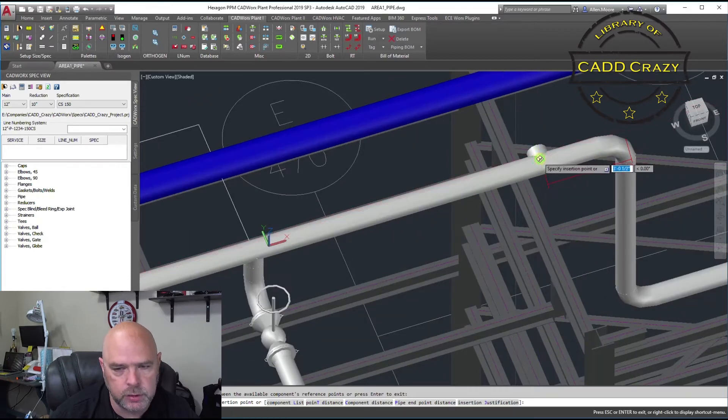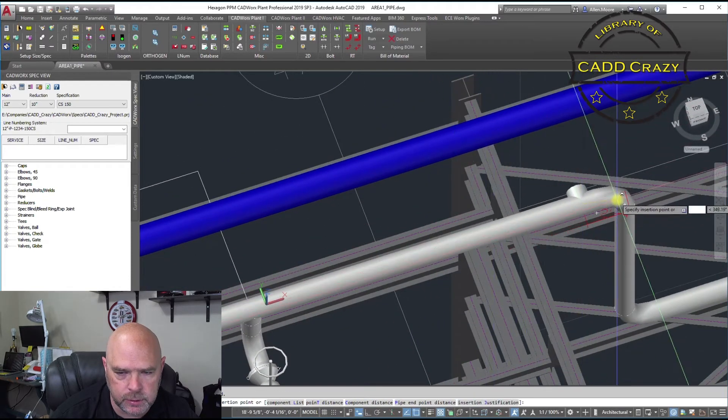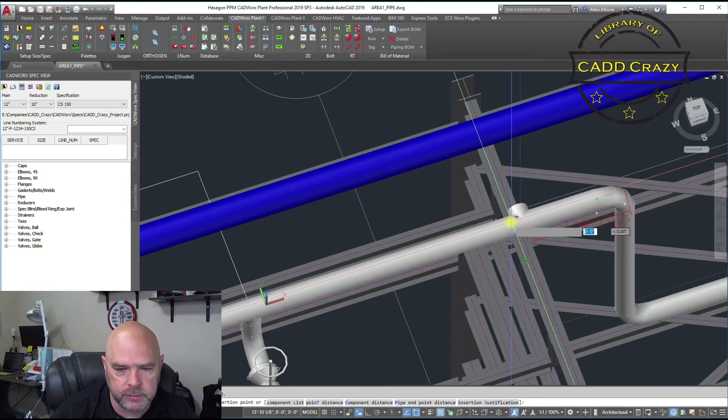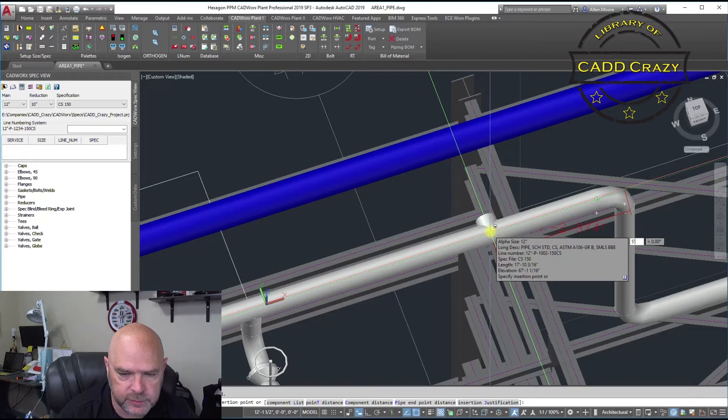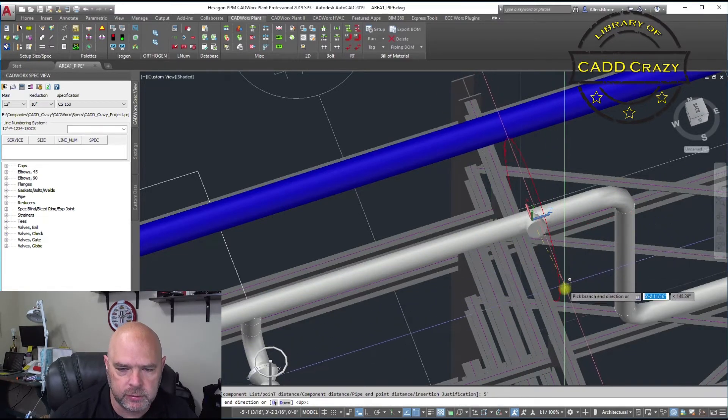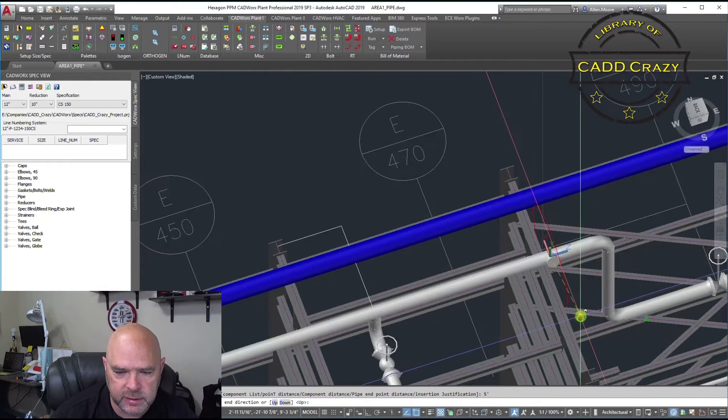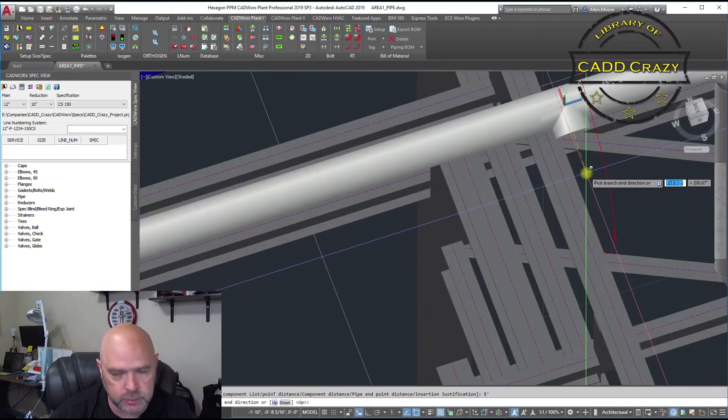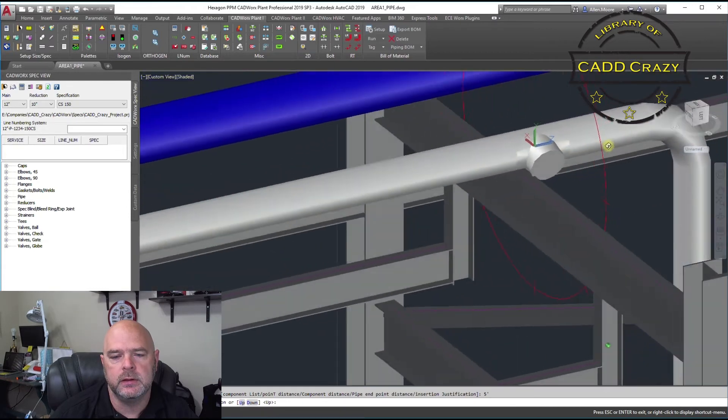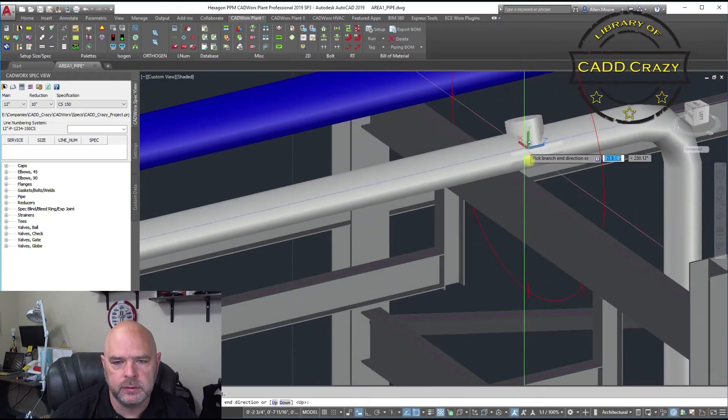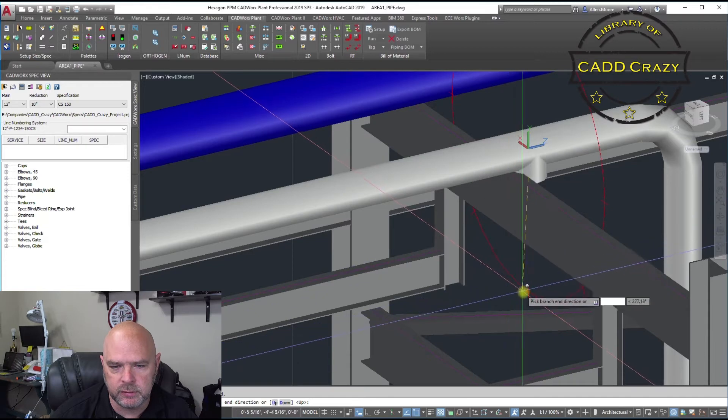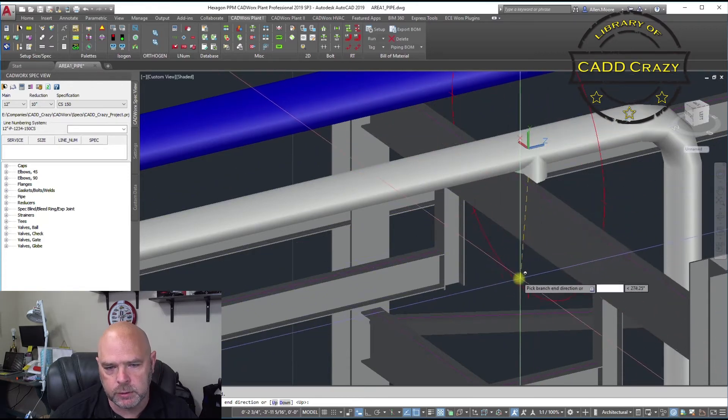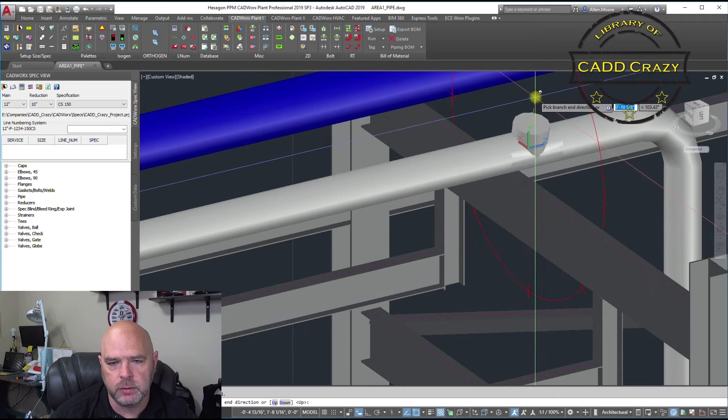If you want to go ahead and just put in a dimension, let's say we want it five feet from that elbow right there. We're going to go five foot. And then it will ask you what direction. Do we want to come off to the side? That's kind of a no-no, especially when you're in a rack. Down, up. So let's go up because if we go down, we'll go right into the steel.